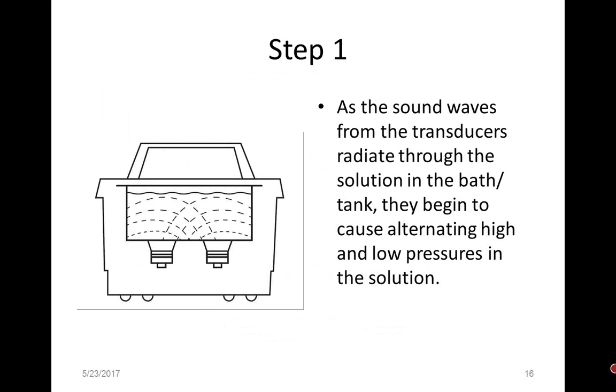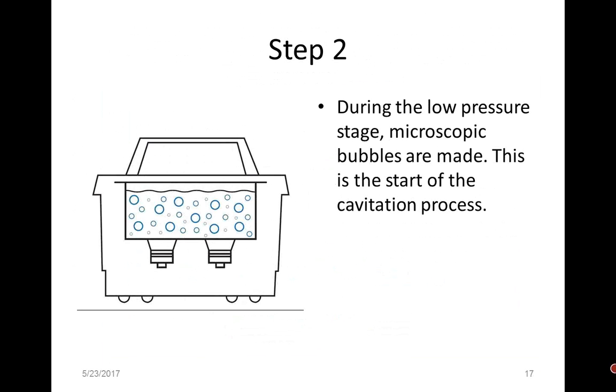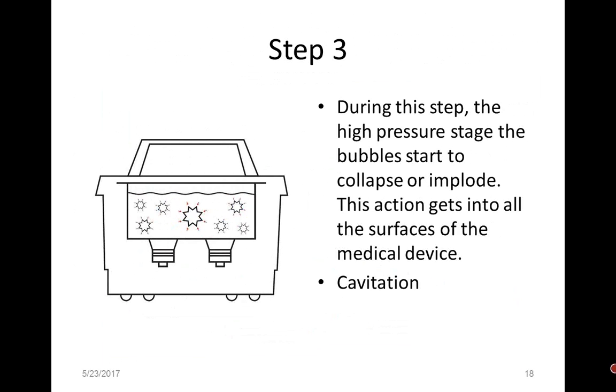So I'm going to break it down into 3 easy steps. If you're into the science of it, I can gladly send you many technical articles that'll break the steps down more. But first, the sound waves from the transducers radiate through the solution in the bath tank. They begin to cause alternating high and low pressure in the solution. Then during the low pressure stage, microscopic bubbles are made. This is the start of the cavitation process.